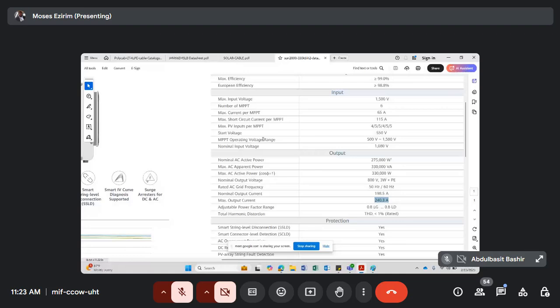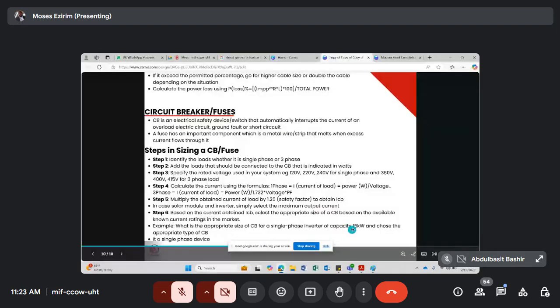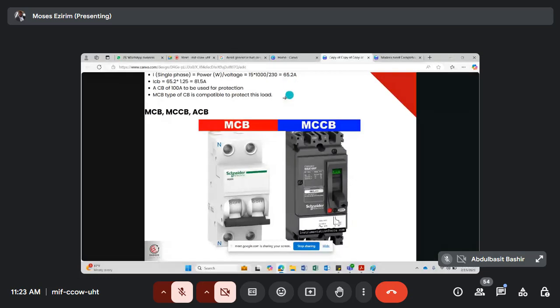What is the appropriate breaker for 15 kilowatts? Choose the appropriate one. All right, now you can see it's a single phase. So since it's a single phase, I'll just divide by the voltage. You can see 65. For those of you that do residential, if you're going to size the output cable, remember an inverter has an input terminal, and for that output, just divide. You can see you have 65.2 amps. 65 amps, you multiply it, you can see 81.5 amps is not in the market. The closest one is 100. A breaker of 100 amps to be used for the protection.